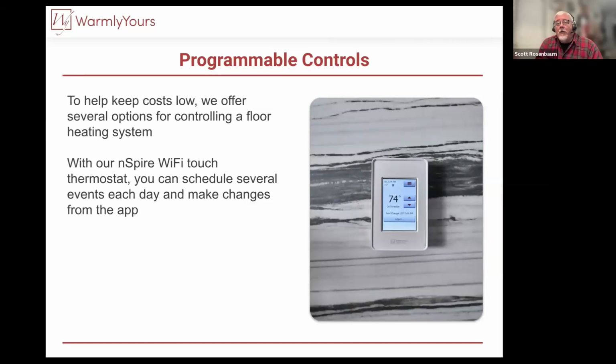Yeah, and I saw what you did there by saying touched on, because that is a touch thermostat you have there. So it's important to know whether your floor can have a programmable thermostat or not, because some hardwood floors don't let you set back the temperature. Some carpet floors don't let you set back. They'll say you must keep this flooring at the same temperature 24/7. Maximum deviation 1 or 2 degrees. Well, if that's the case, you don't want to use a programmable thermostat because you can't set it any lower and you can't set it any higher. You just have to keep it where it is.